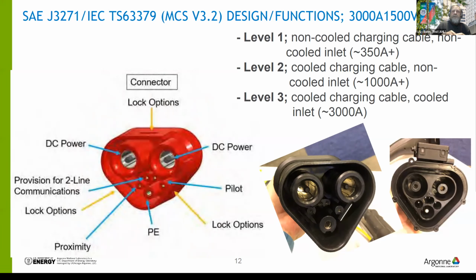In the lower center, you can see what's called PE, or protective earth, and that's like your tools and appliances. If there's a short in the battery, all the fault current goes down there, and we test to 100,000 amp short circuit peak, or 3 mega amp squared seconds, if anybody understands what that number means. And then there's the pilot, which signals communication interlock and auxiliary power.